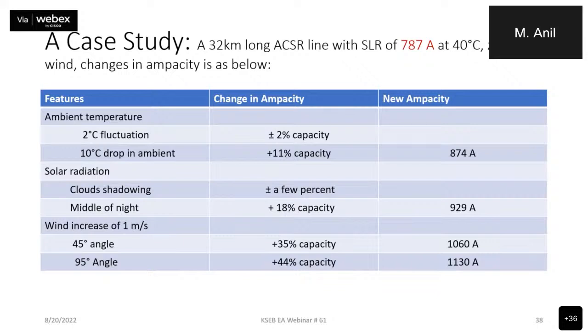So much of a difference could be achieved with a 10 degrees Celsius drop in ambient temperature. Then regarding solar radiation, if cloud shadows are present, then plus or minus a few percent can be achieved due to the absence of sun. But in the middle of the night, a plus 18% capacity enhancement can be achieved. That means instead of the SLR, static line rating, of 787 ampere, we can throughput 929 ampere in the middle of the night, with an 18% ampacity rise.